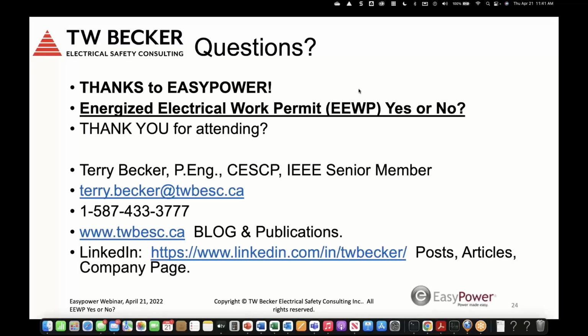Well, no, because the batteries are always going to have voltage present. So how do we disconnect the batteries without voltage present? The permit doesn't apply. If we need to work on batteries greater than 125 volts DC, there is arc flash and shock hazard, so you manage that risk with boundaries and PPE, but you don't need a permit to work on batteries—because how else do we work on them, to disconnect them, to replace them, to do measurements if needed? We can't get rid of the voltage.